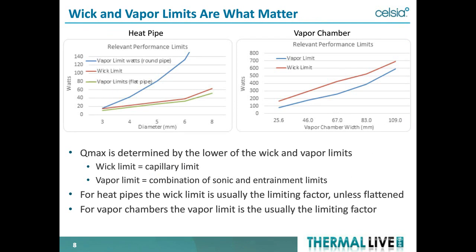Looking at performance charts: on the left are heat pipe performance limits by diameter, and on the right vapor chamber limits by width. The blue line shows the vapor limit; the red line shows the wick limit. The wick limit is the limiting factor until you start to flatten heat pipes — once you flatten them, the vapor limit generally comes down in line with the wick limit. For ultra-thin devices, optimizing the sweet spot between wick limit and vapor limit is key. For vapor chambers, the wick limit is above the vapor limit because they are flattened devices and the vapor space is smaller in a rectangular device versus a round one.